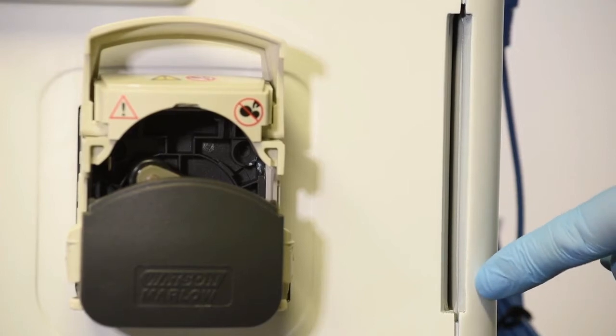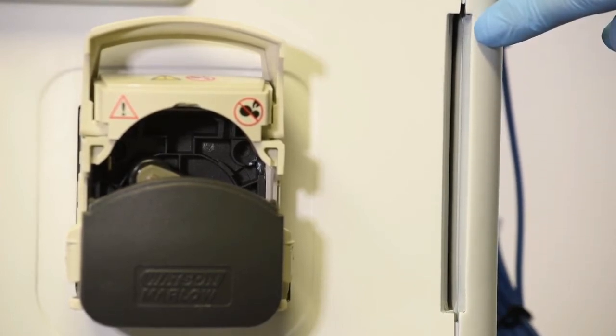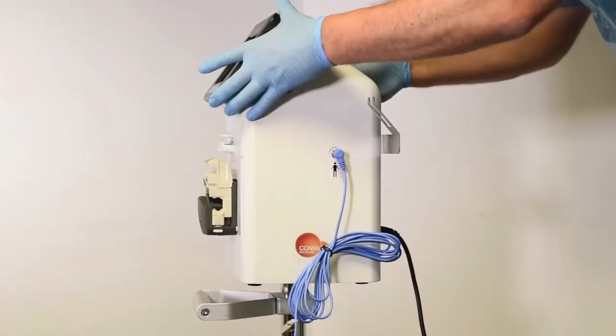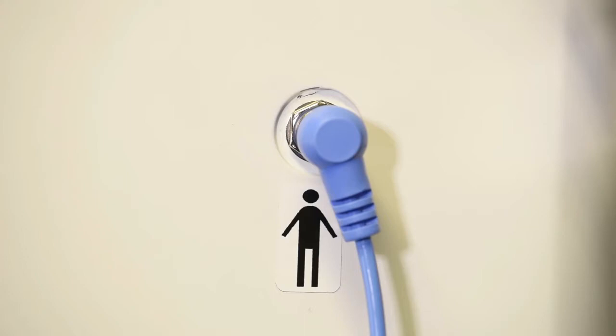The heating plate slot accommodates the heat exchanger of the disposable set, an easy-to-insert innovative aluminium foil heat exchanger that provides effective and accurate heat control and transfer. It requires a low priming volume and consequently minimizes dilution of the chemotherapy agent. Temperature probe port enables the accurate continuous monitoring throughout treatment from the inline fluid temperature probe of the disposable set.